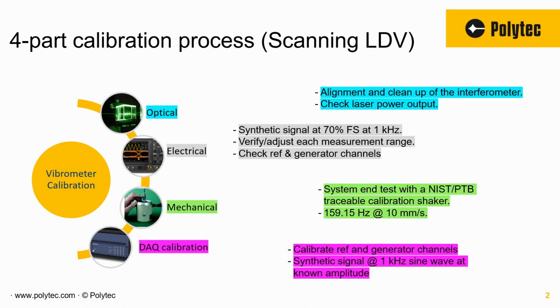All right. Now that we know what the steps are, here's a 1-slide summary of what Andrew just explained. 4 steps. The first 3 are similar or the same as single point vibrometer calibration with some differences: the optical, electrical, and mechanical, with the optical alignment and laser power output check. Then we do the synthetic signal insertion and do the electrical calibration. And then we top it off with a mechanical end test. What's different is step number 4, the data acquisition calibration, which is an integral part of the scanning LDV. So that is also done and is an additional step when it comes to scanning vibrometer calibrations.